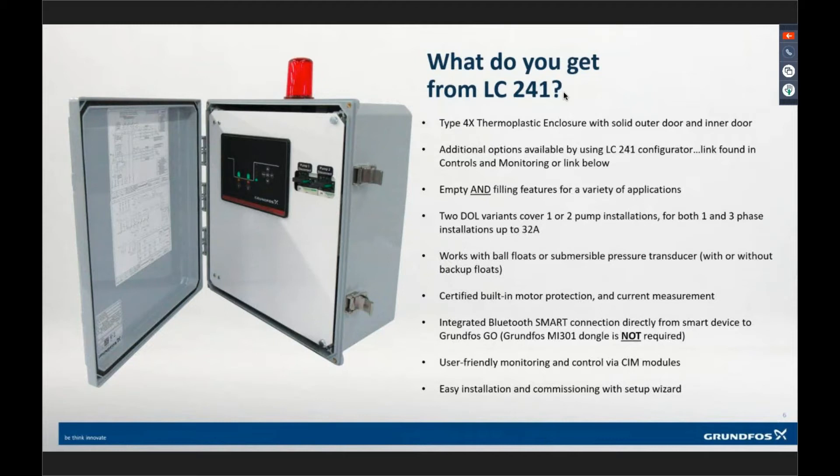If that pump trips out on the overload, you have to manually reset it on this model. It will work with ball floats or transducers. We have a one- and two-pump variant, covering single and three-phase applications. The only standard single-phase variant is for our two-horsepower SEG single-phase pump — it has the external capacitors and is size-specific to that two-horsepower SEG pump. The three-phase variants don't require the neutral — that's only for the LC231.